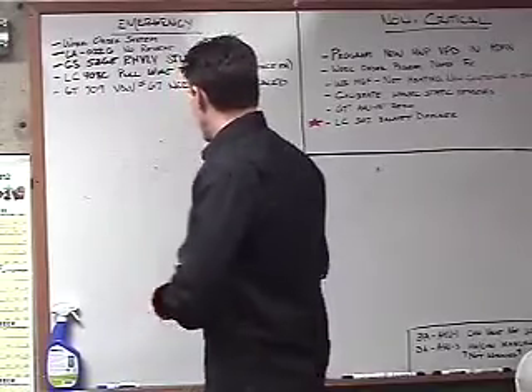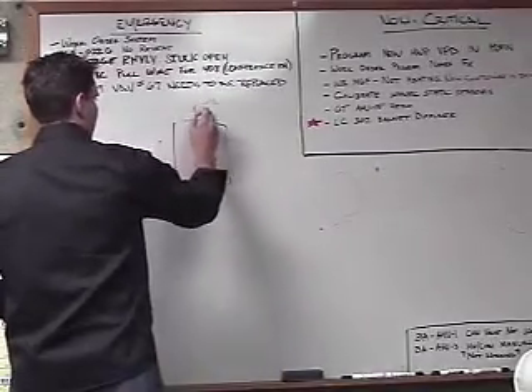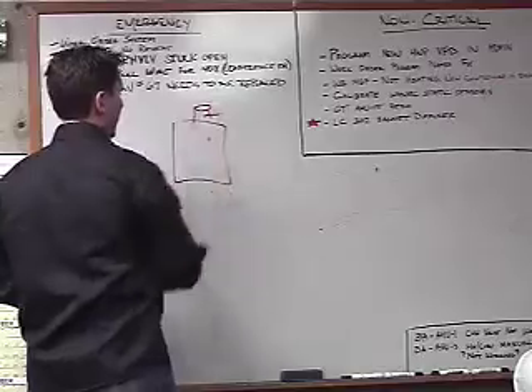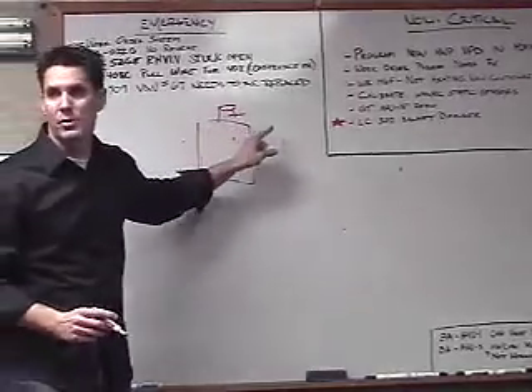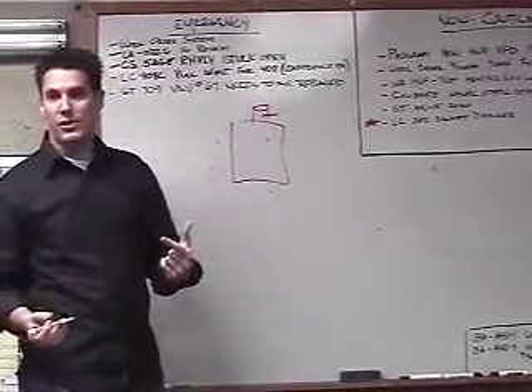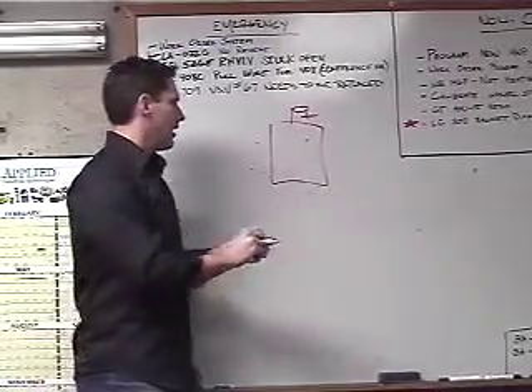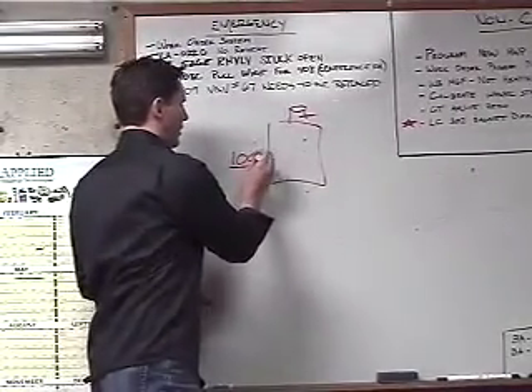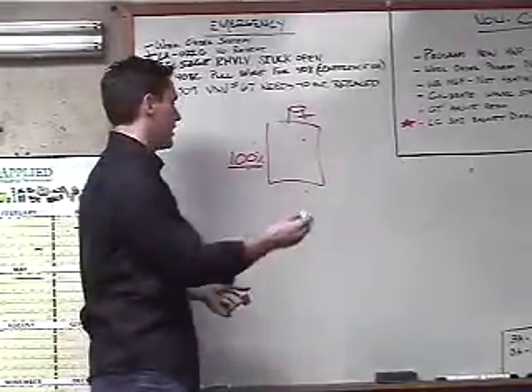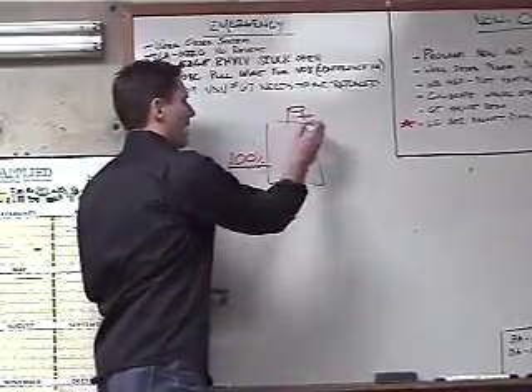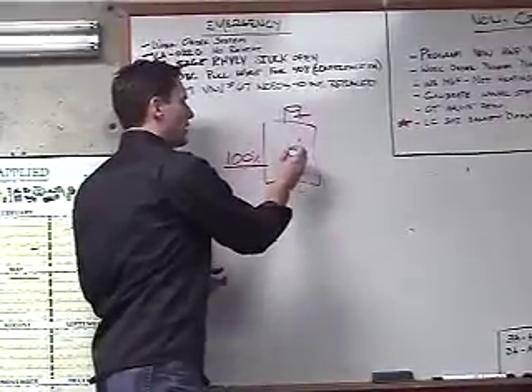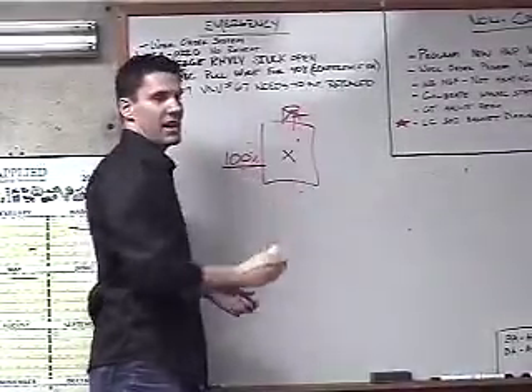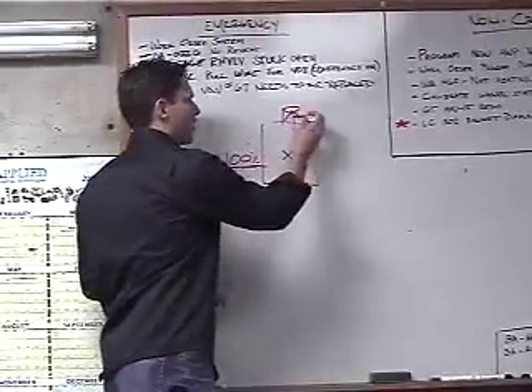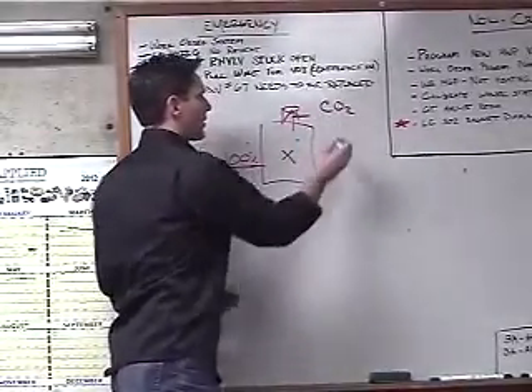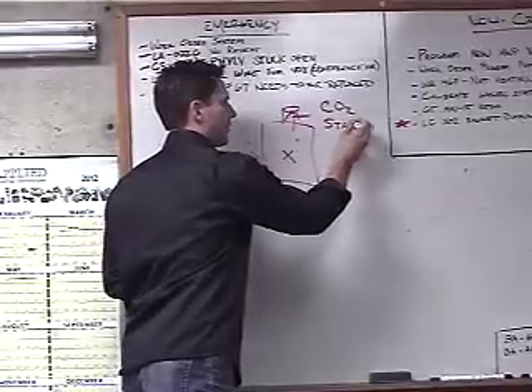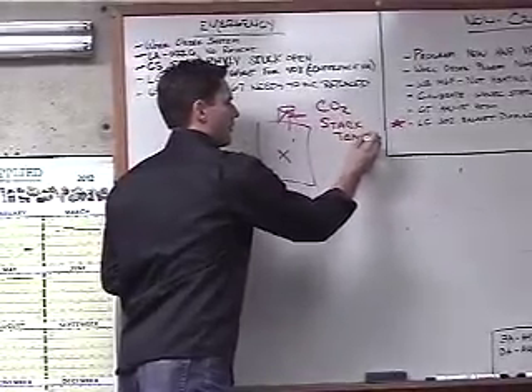Combustion efficiency: if I have a boiler, I've got my stack coming off the top of my boiler, I put in my probe here, this is where I'm going to measure it, and all I'm doing with combustion efficiency is measuring how much heat I create. I'm sending in 100%, so my boiler's operating at 100% fire capacity, sending 100% of my fuel. How much of that heat that I create is being used in my process and how much is going up the stack? So what we do is we measure our CO2 and we also measure our stack temperature.